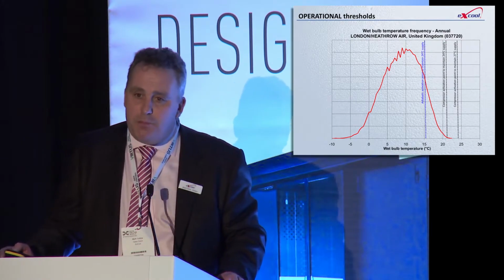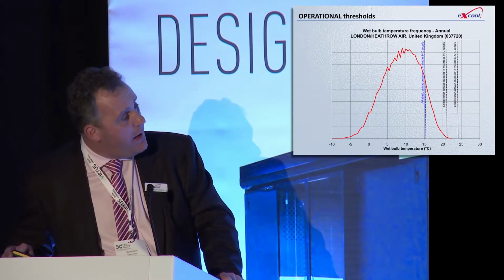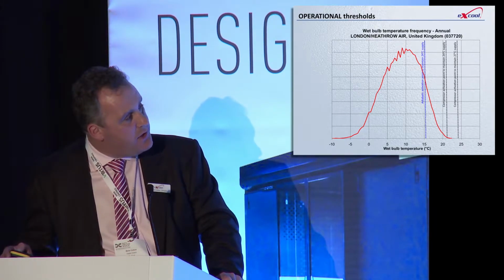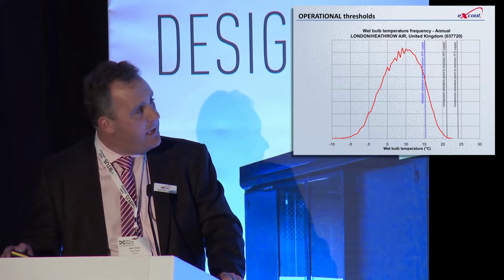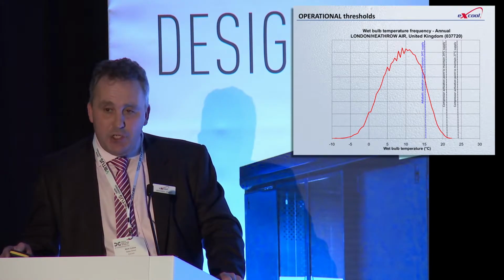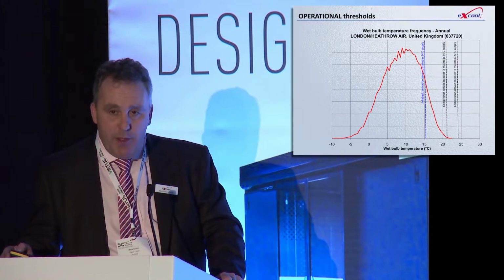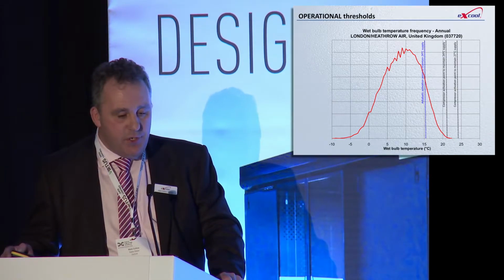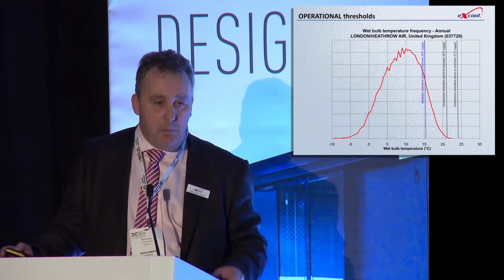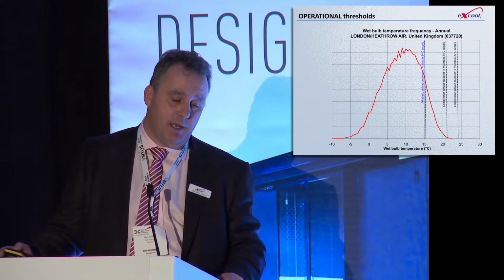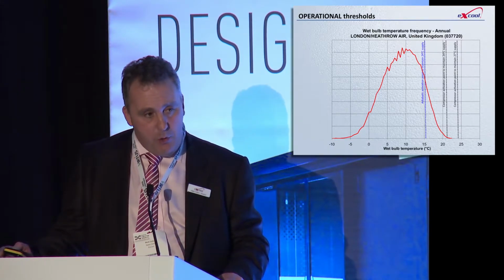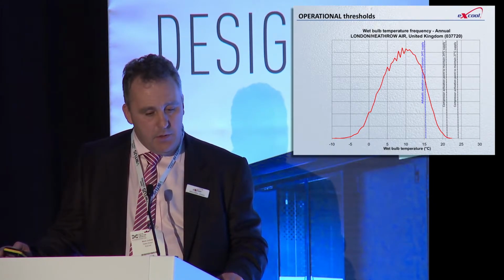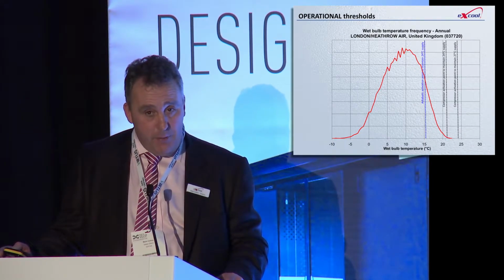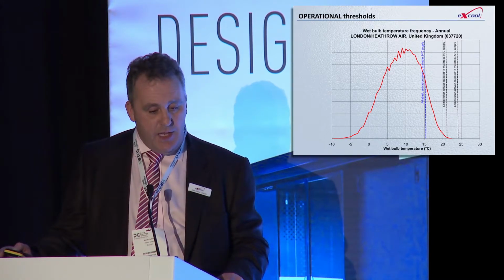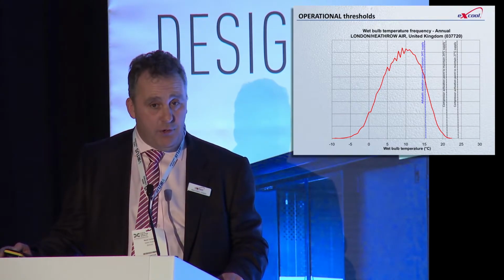So this is what a wet bulb temperature gradient looks like for London, for Heathrow Airport. The wet bulb temperature rises to around 22.5 degrees C on a peak day. For us to maintain 24 degrees C supply, which is generally where most of our clients want to sit, we would need to introduce moisture to the outdoor airstream where that blue line crosses the temperature gradient. So around 15.5 degrees C wet bulb, we start to introduce moisture. The compressors would be needed to maintain 24, remember, at this point here. So you can see the area that's left under that graph is very, very small. It's a couple of hours a year to maintain 24 degrees C.